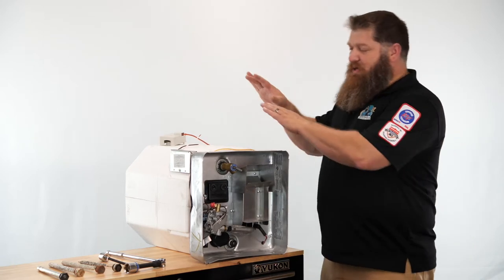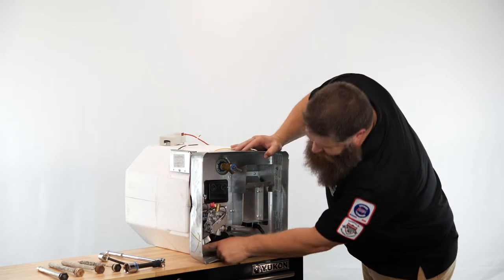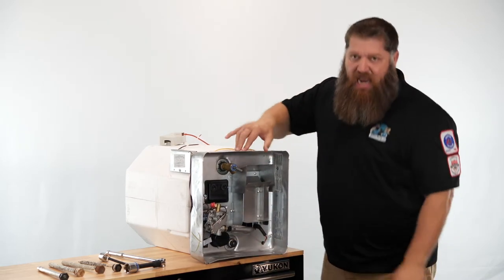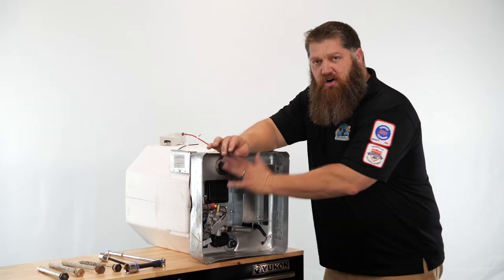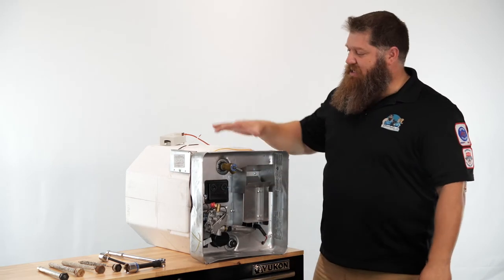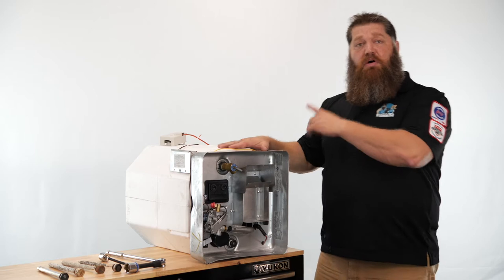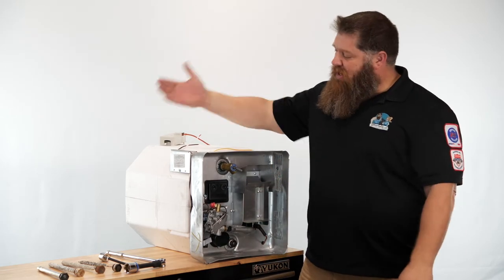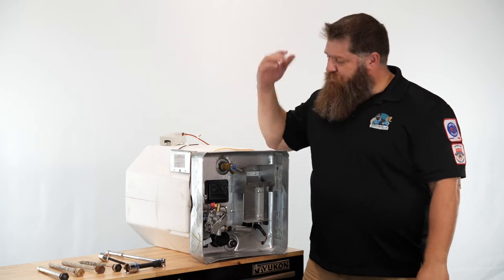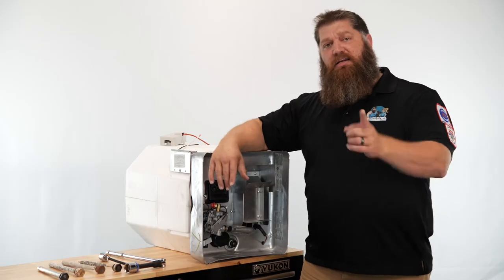So what we can do is we can turn off the water flow to this and turn off the power. Once we turn off the power there's no longer any heat taking place inside our water tank. So we'll go over to a water faucet. Over at the hot side we're going to open that up. We're going to let all the hot water drain out. And once we feel that we have cold water coming out our hot water we're ready to go to our next step.